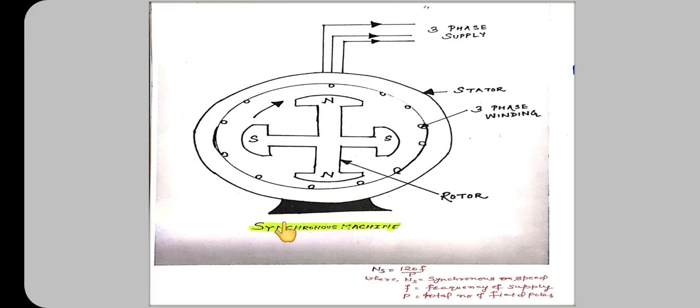The armature winding can be more easily braced in a rigid frame to prevent any deformation which could be developed by the mechanical stress set up due to the high speed of rotation. The armature winding is cooled more easily because the stator core is made large enough with many air passages and cooling ducts for forced air circulation.